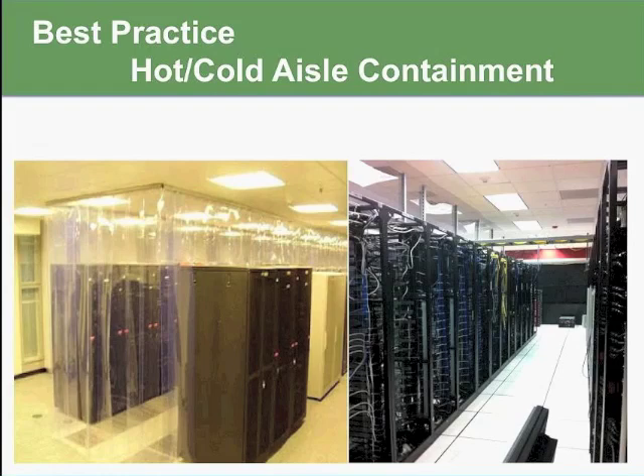The photo on the left shows your meat locker type containment, where you have curtains that are separating the cold air from the hot air. In this case, it's a cold aisle containment because you can see the perforated floor tiles blowing the cold air into the cold air aisle, and the curtains are keeping the cold air and the hot air from mixing. On the right-hand side is a little more sophisticated implementation of your containment where you're using more plexiglass, and you have, in this case, some solid sliding doors at the ends of your aisles to prevent the mixing.